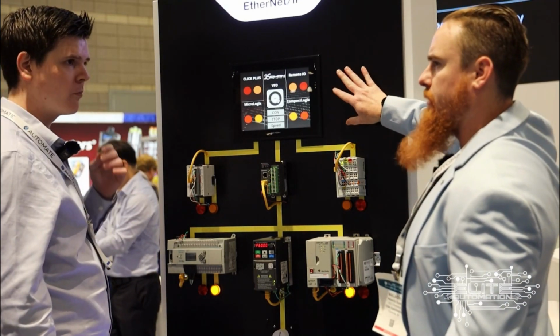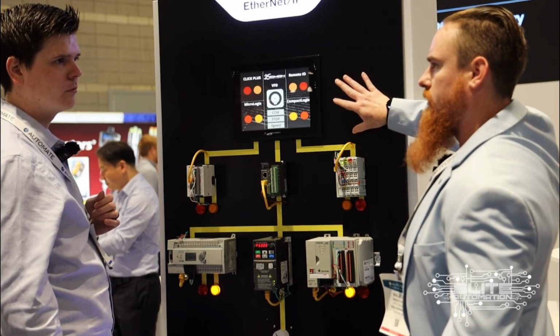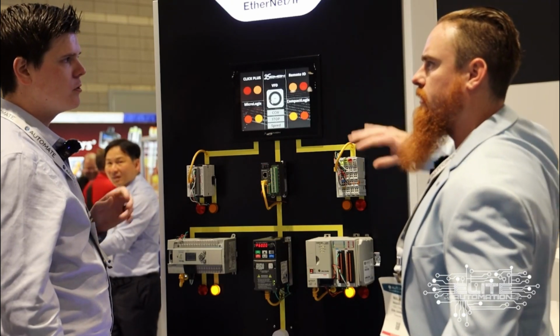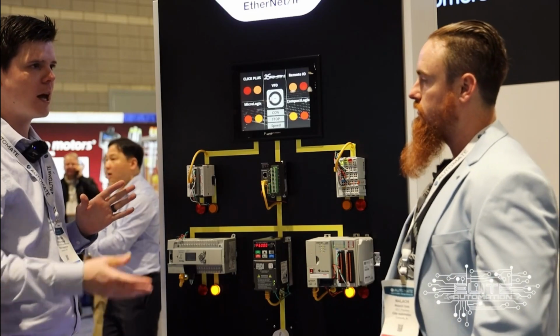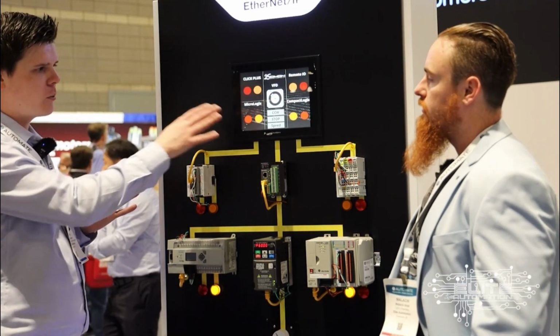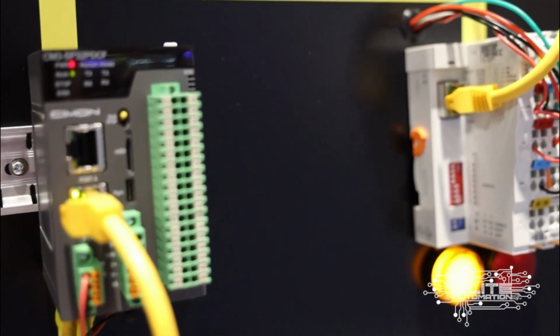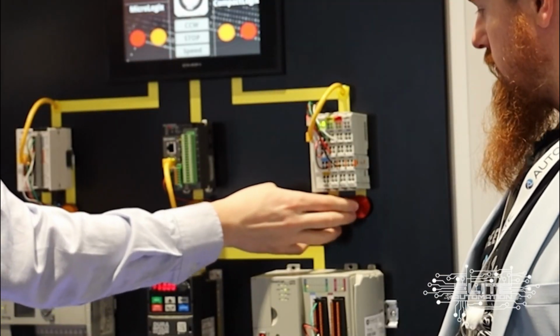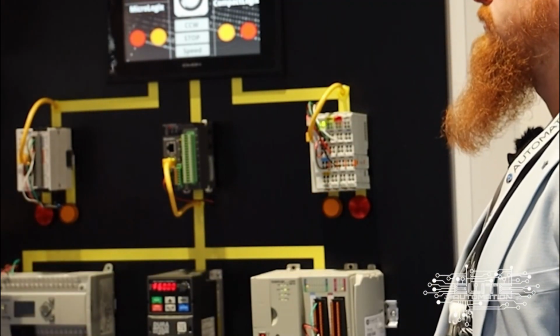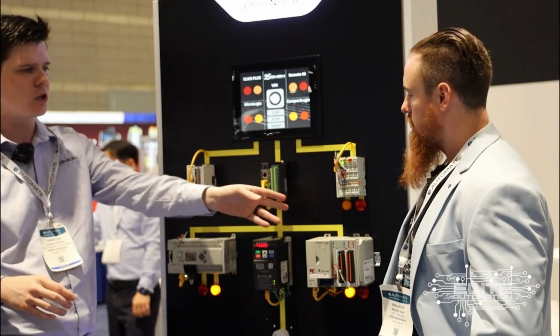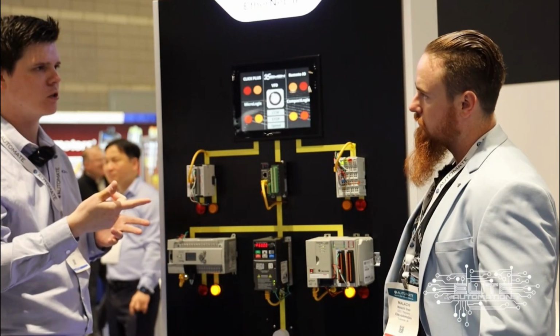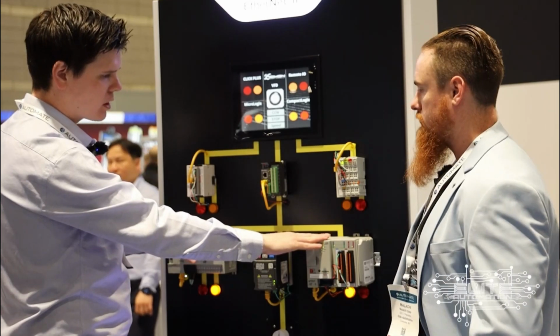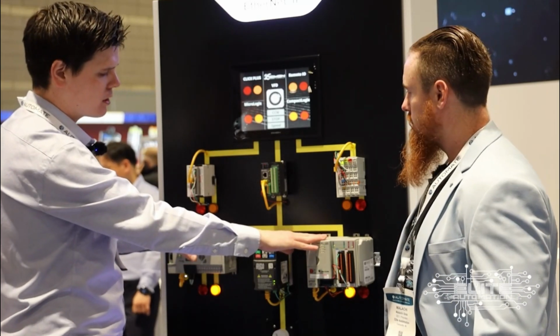I'd say, at least this version doesn't have logic, where you could really write logic in it? No, it does. Actually, it has JavaScript. You can have a scripting engine for JavaScript. That's actually what's controlling the logic right now. If I recall how I set it up, each tag can have a defined action when a value changes. And that's what I'm doing here. When this value changes, I have this go on. So that's why it's toggling off and on. So you can use a scripting engine for JavaScript, or you can just do tag-based actions when a value changes. Okay. So then ControlLogix and CompactLogix, or CompactLogix and MicroLogix, as people are aware, right?